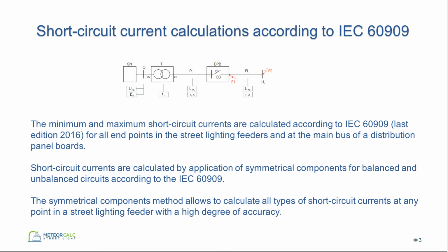MeteorCalc performs the short circuit current calculations by the symmetrical components method. You can calculate a short circuit current at any endpoint of street lighting feeder or at the main bus of a distribution panel board.